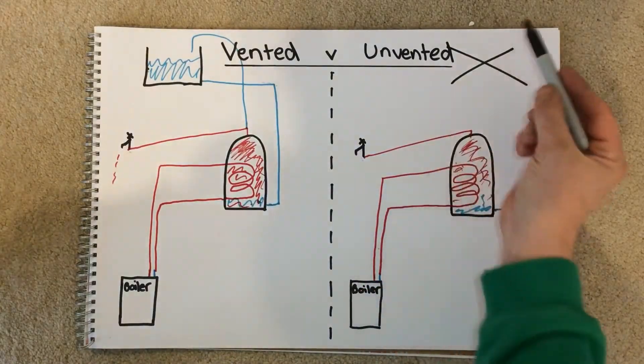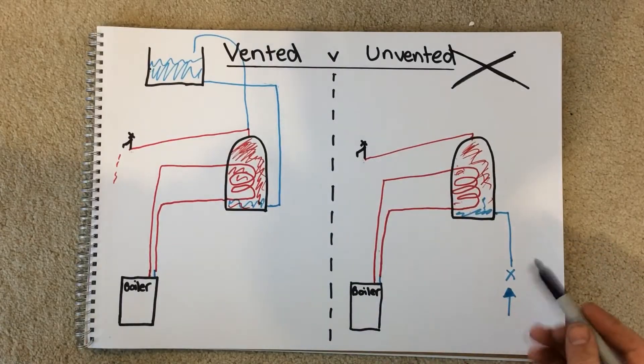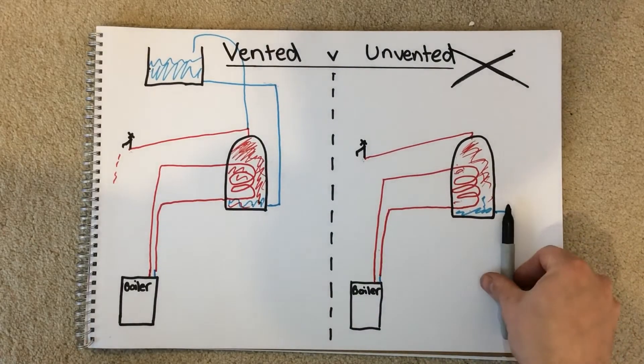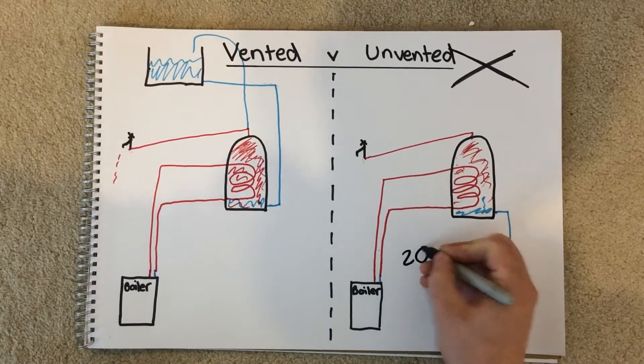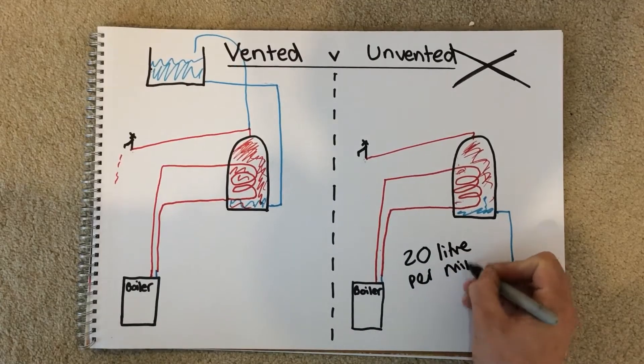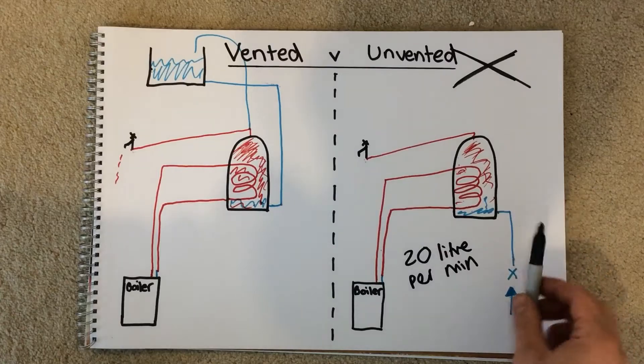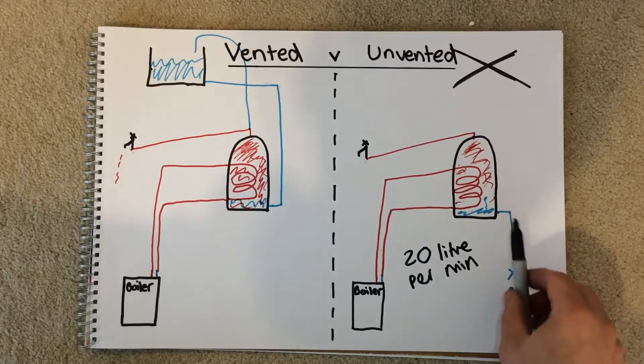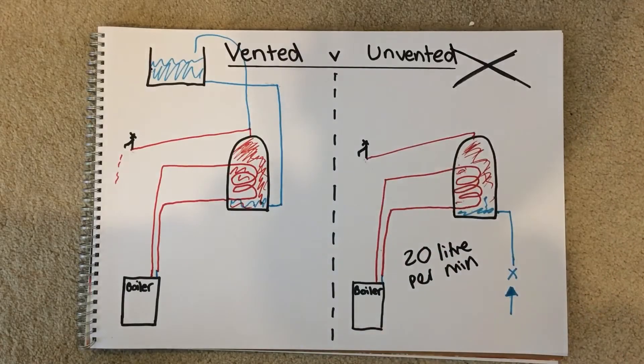Your unvented does away with the tank in the loft and it's fed via the mains in the ground. What you do need though is a minimum of 20 litres per minute. The main reason for this is to make sure that there's enough demand coming into the cylinder to supply your taps and your showers in your house.